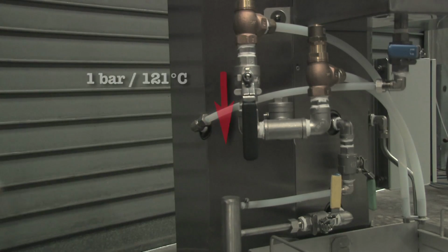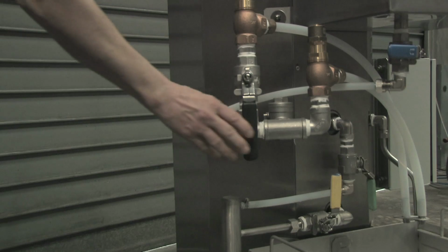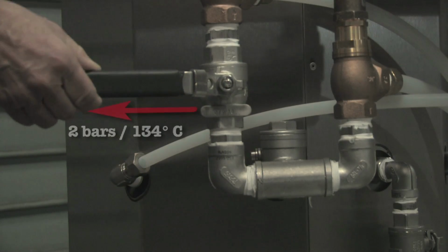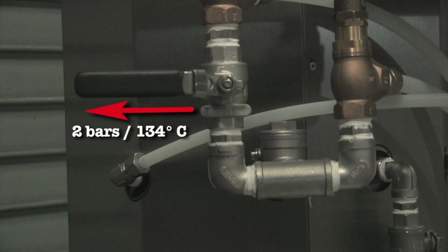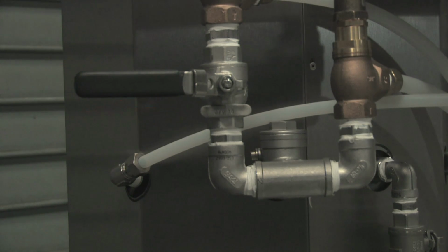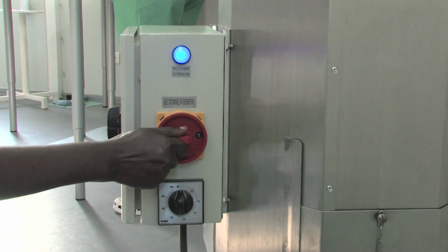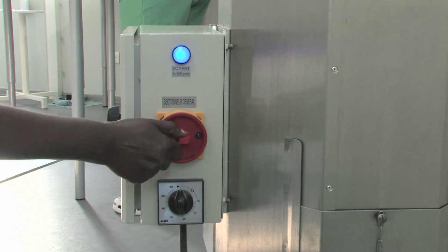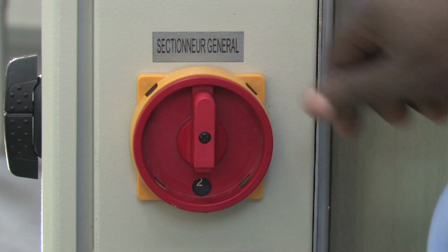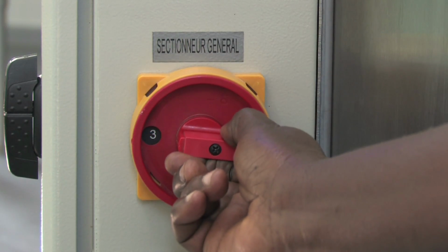On newer models, when the black valve is open, the relative pressure will reach 1 bar, that is a steam temperature of 121 degrees Celsius. And when the black valve is closed, the relative pressure will reach 2 bars, or a steam temperature of 134 degrees Celsius. 2. Start the autoclave at maximum power, that is in position 3.